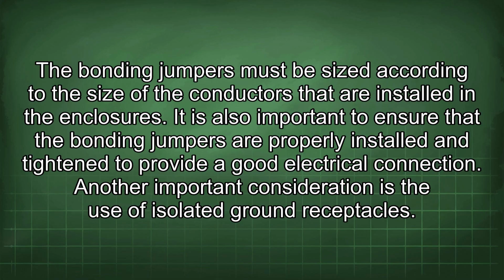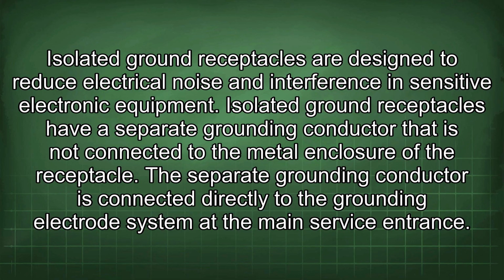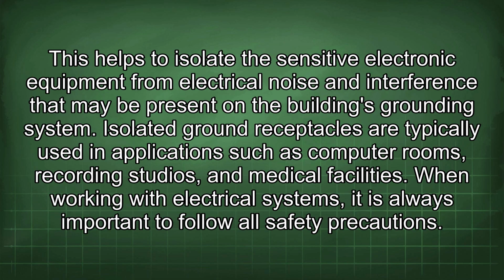Another important consideration is the use of isolated ground receptacles. Isolated ground receptacles are designed to reduce electrical noise and interference in sensitive electronic equipment. Isolated ground receptacles have a separate grounding conductor that is not connected to the metal enclosure of the receptacle. The separate grounding conductor is connected directly to the grounding electrode system at the main service entrance. This helps to isolate the sensitive electronic equipment from electrical noise and interference that may be present in the building's grounding system. Isolated ground receptacles are typically used in applications such as computer rooms, recording studios, and medical facilities.